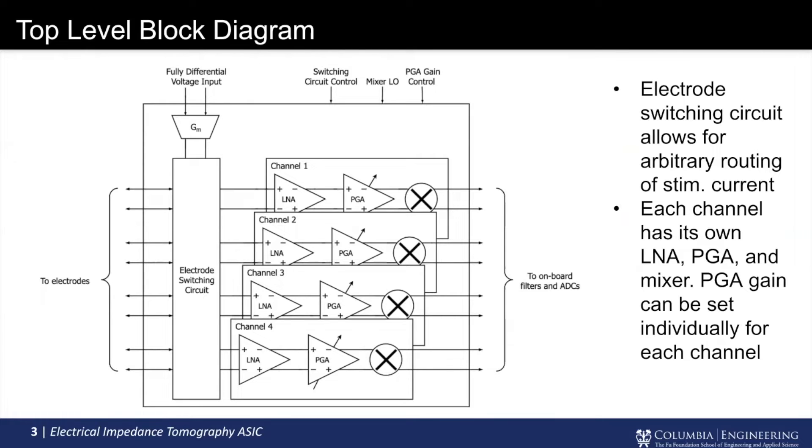And then connected on the other side of the electrode switching circuit are four channels, which are identical. Each one of them has an LNA, which has a gain of 20 dB, a PGA, which has a gain from 0 to 42 dB in 6 dB steps, and a mixer. And then after it goes off of the chip, it goes to the onboard buffers, filters, and then ADCs.